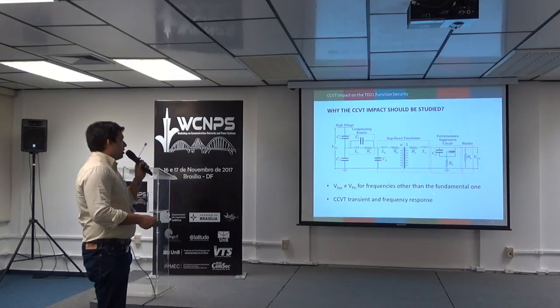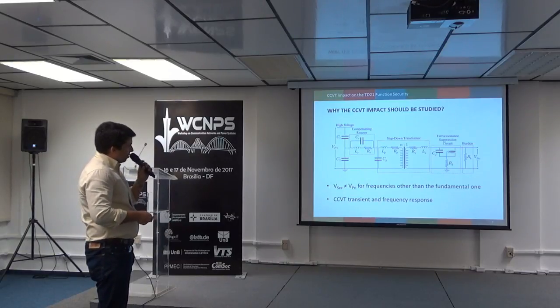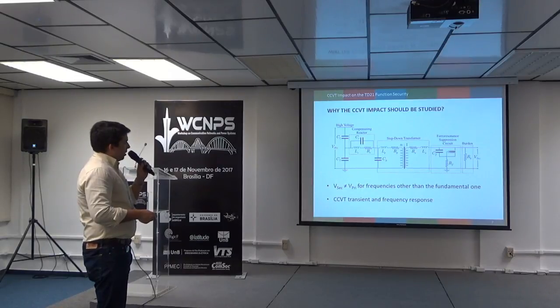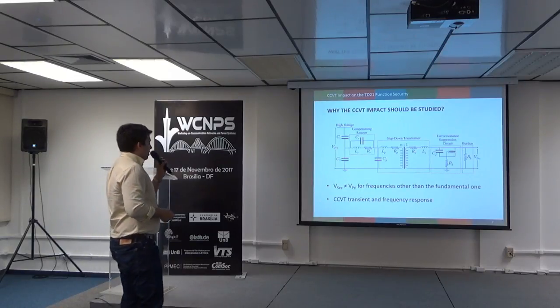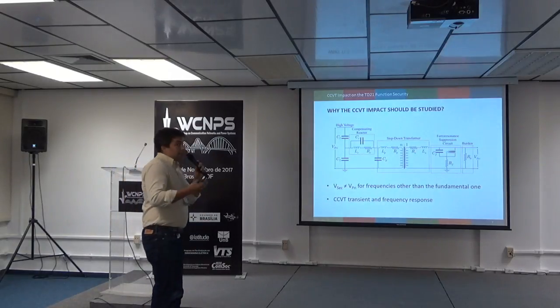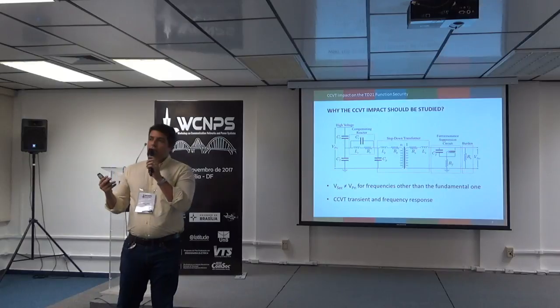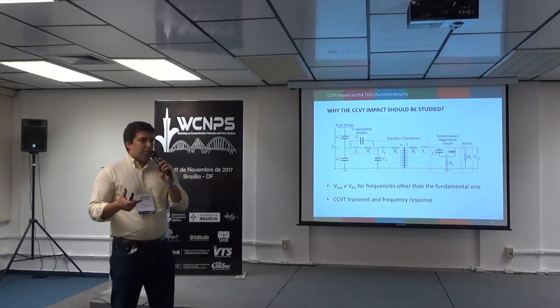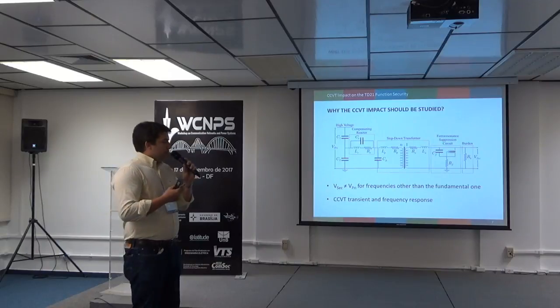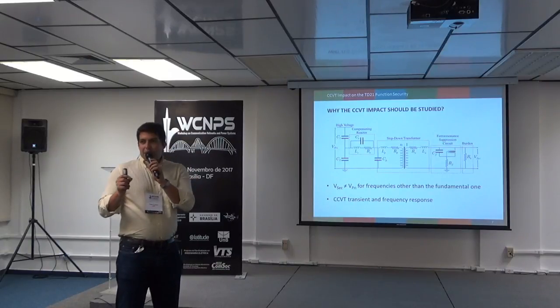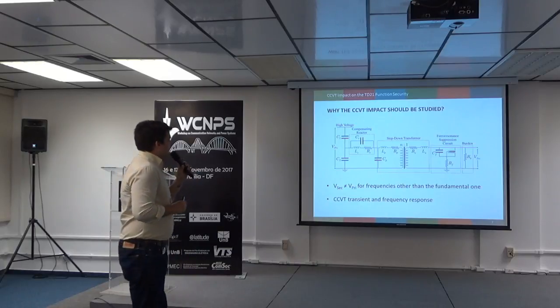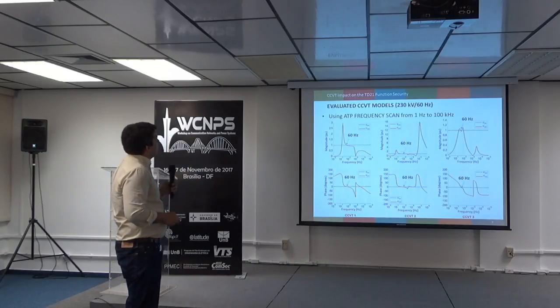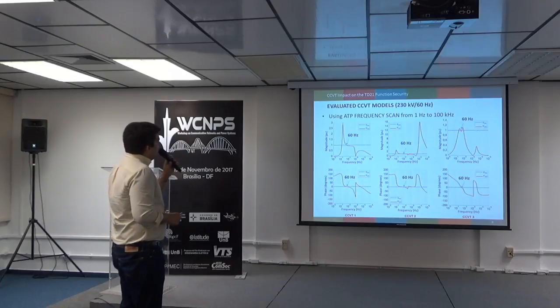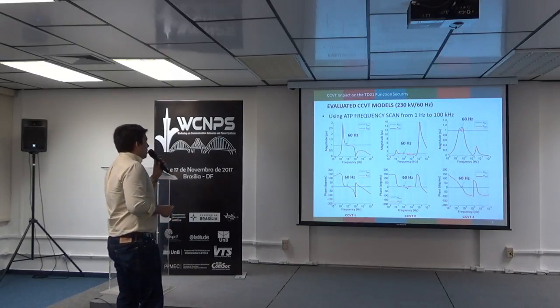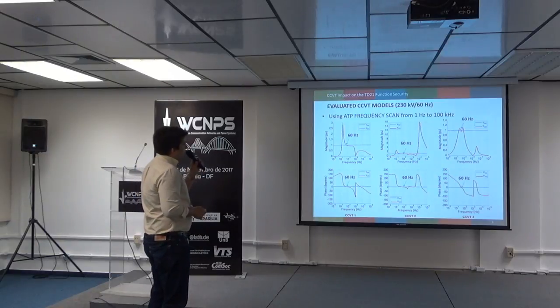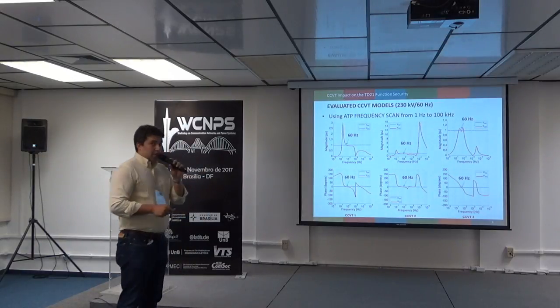For frequencies other than the fundamental one, the secondary voltage is not the same as that found in the primary windings. So due to that, we have two problems: the transient response and the frequency response. These two problems are a little bit different and may cause different problems for our function. To illustrate this, the ATP frequency scan was used to estimate the frequency response of three CCVT models found in the open literature.